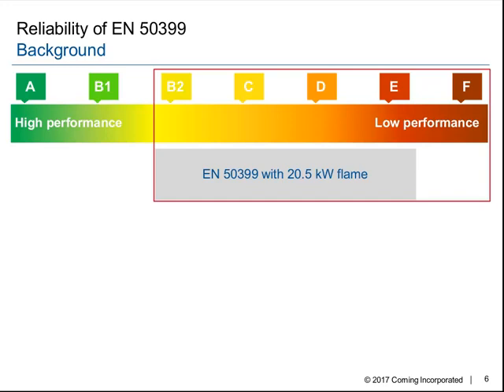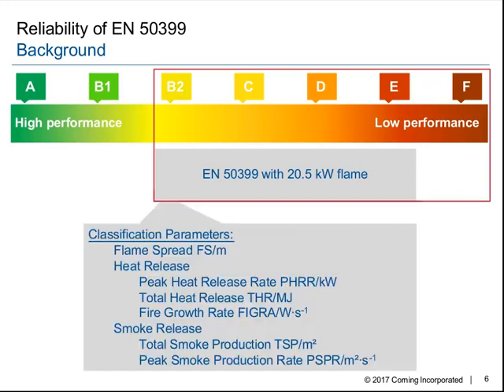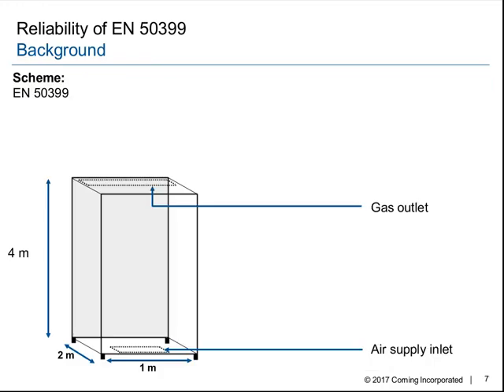And one of the tests which is mainly determining the class is this EN50399 test with a 20.5 kilowatt flame. This test delivers certain parameters, so the flame spread, the burnt length along the ladder in meter, some heat release, and some smoke release parameters. Based on those parameters, the class is determined. So let's have a look on the test.